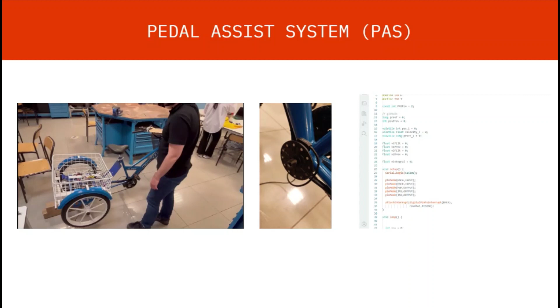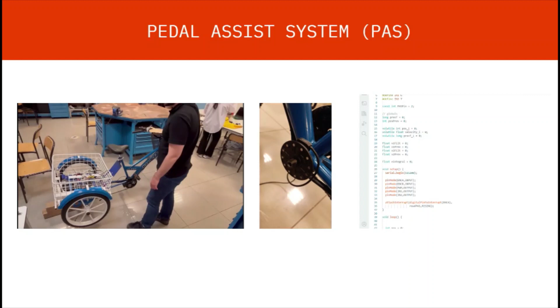Several tests were run and a PI control was designed to control the motor precisely. In the first test, motor speed stayed under the set points; after tweaking Kp and Ki parameters to reach the set point, the ride was pretty smooth enough to travel around.